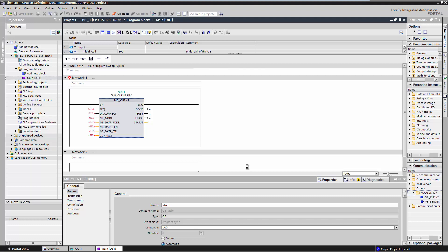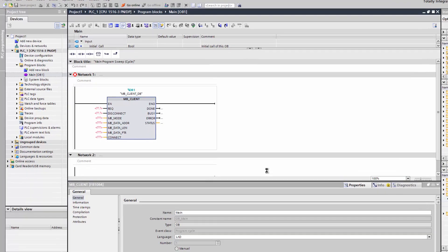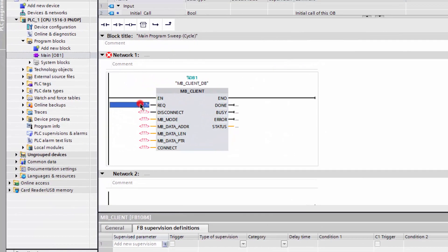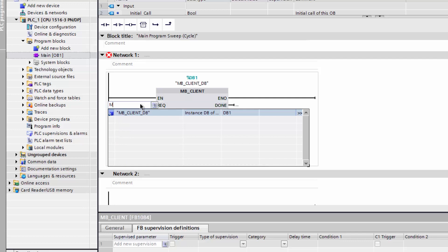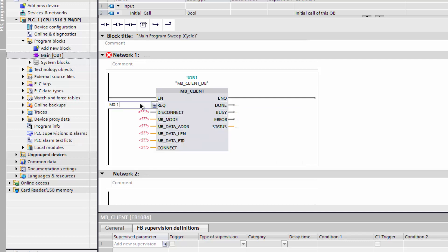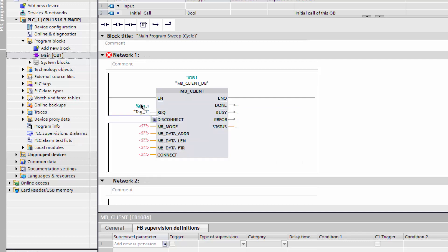The parameter REQ stands for Modbus request and is level controlled. Define a variable for the parameter to send a communication request. The Disconnect parameter is used to control the establishing and termination of the connection to the Modbus server. Set it to false to establish a connection.